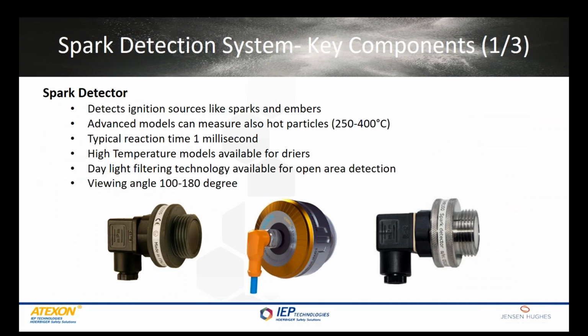Now we are going to go through the key components of a spark detection system. The first one is the spark detector, which is the most important one, because if this small device fails or is not capable of detecting ignition sources, then the rest of the system is useless. Typical parameters for spark detectors are listed here, and they are an ability to detect a various range of ignition sources like sparks and hot particles. Typical reaction time is only 1 millisecond. They are very rapid. High temperature versions are also available for dryers and ovens. And daylight filtering possibilities and viewing angle properties we already discussed during previous slides.